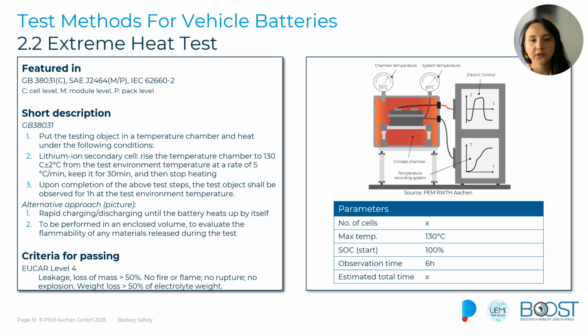Another scenario here is the extreme heat scenario. In this case, the battery is going to be exposed to very high temperatures, up to 130 degrees, for instance. And this may be done by putting the battery inside of a climate chamber or by simulating scenarios where the battery heats itself through rapid charge and rapid discharge cycles. This is another test that is very important because excessive heat is one of the most common triggers for thermal runaway, which in the end will lead to fires and explosions in our batteries. So with this test, we want to ensure that even in extreme temperature conditions, the battery will stay safe.